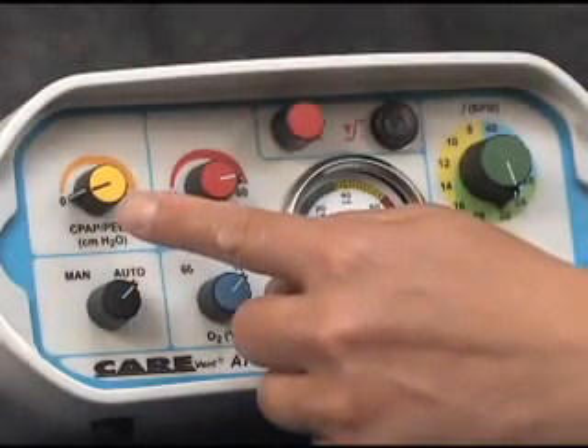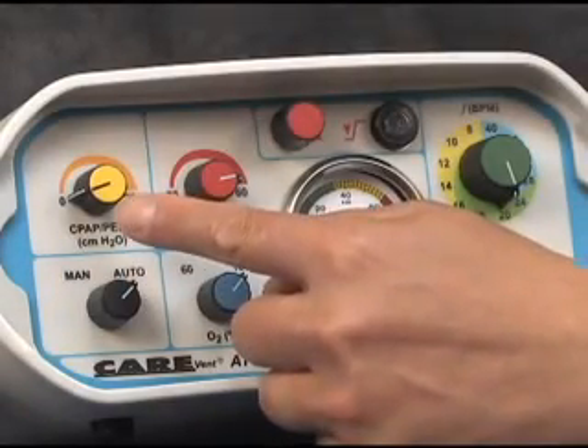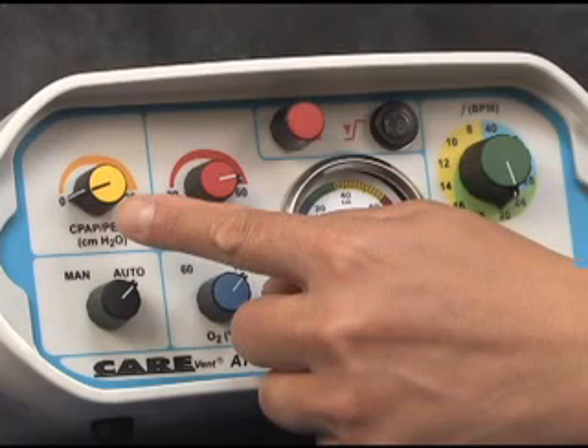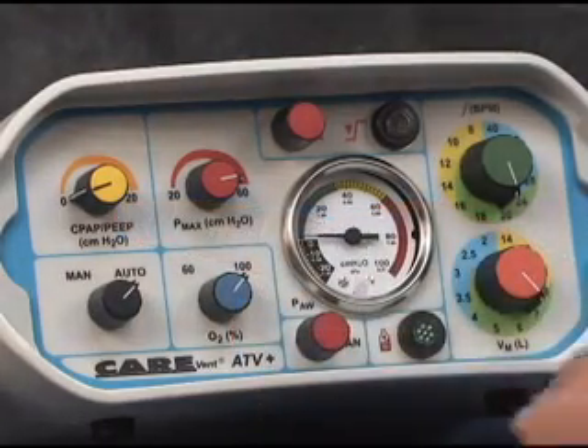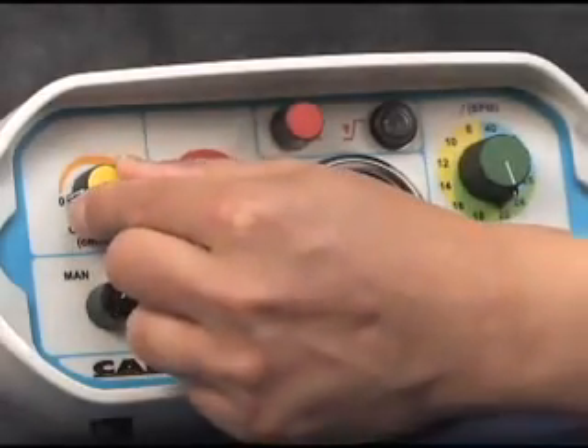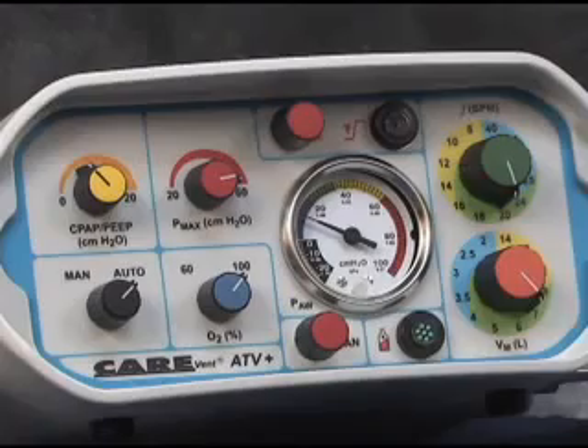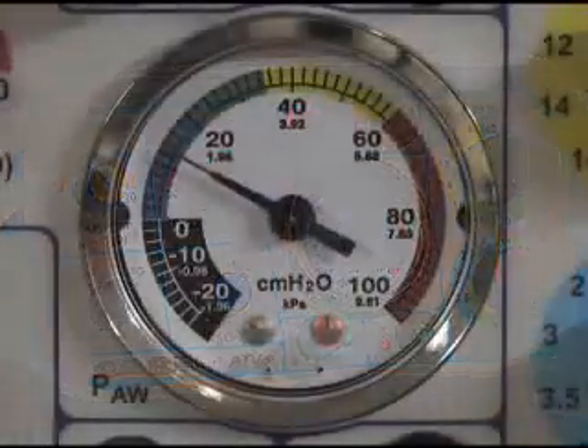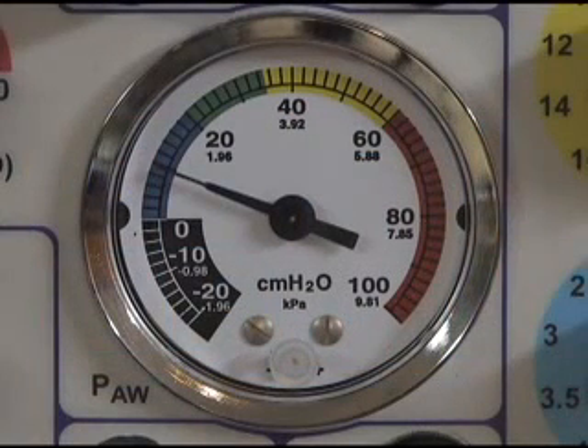A CPAP PEEP control is provided on the ATV Plus and MRI ventilators, which allows for the use of these functions without the need for an external PEEP valve. The airway pressure baseline is elevated to increase the resistance to expiration at the patient valve, thereby maintaining the airway in an open state. As the control is rotated, you will hear gas flowing, confirming that the control is functioning.